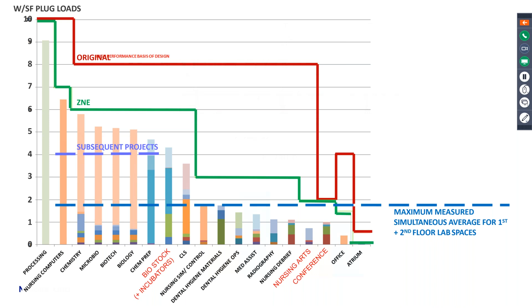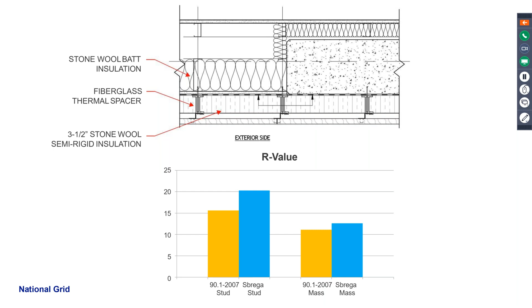Now, normally for a lab building, the envelope is not a big driver, but once we reduced all of the other loads so dramatically, it actually became important for us to enhance the envelope and at least meet the code requirements for both the mass and stud wall assemblies. Many buildings, particularly back 6-7 years ago when this was in design, did not carefully address things like thermal bridging, and we made sure to do so.